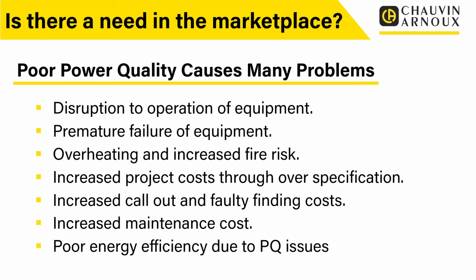We can have increased project costs through overspecification, because by not properly measuring the parameters, we end up overspeccing things like transformers or generators, and we lose money that way. We get increased call-out and fault-finding costs, increased failure rates, faults that are hard to find, things tripping off for no reason. All of these can be indications of power quality problems, and all of this can be summarised under increased maintenance costs.